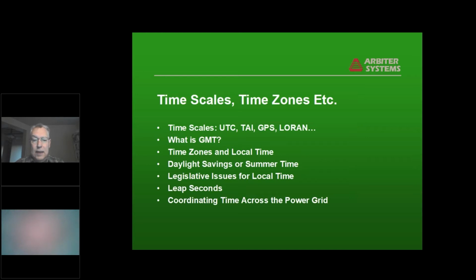One of the things you get into when you start learning about using time is the fact that we've got all these different time scales and leap seconds and other issues, daylight savings jumps. And that can cause problems if one utility is on a different time than another and they're trying to exchange event records, let's say, after a fault. And the most obvious thing is if one's in the Eastern time zone and the neighboring one is in the Central time zone, you're going to be an hour off.